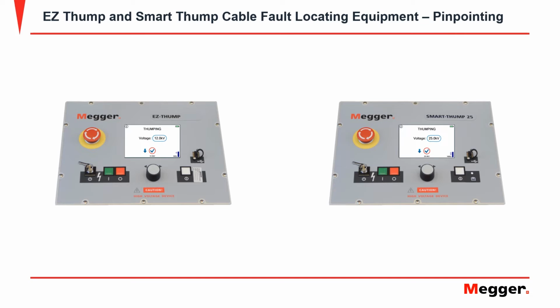With the Smart Thump 25, the maximum kV output is 25, but since this has a dual capacitor, you'll get 1600 joules at 25 kV and also at 12.5 kV. The reason for the dual capacitors is so if you have to thump at a smaller voltage, you'll still get the joule or the full maximum noise output of the thumping. That way at 12.5 you see that you have 1600 joules, but if you just go up 100 volts, you're back down to about 400 joules.